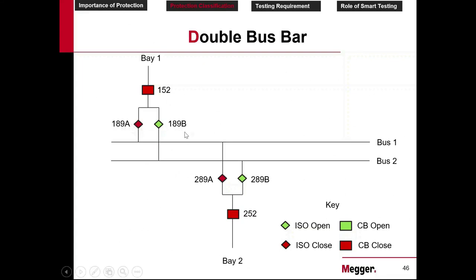A and B represent the isolators: A is the isolator connected to bus 1, B is the isolator connected to bus 2. So 189A means bay 1, the ANSI code of isolator, that is 89, and A represents the bus 1 connection. In this you can have 20, 30 or 40 bays. It will be the same thing repeated in that nomenclature. So let's follow the red line, how the current is feeding or transporting. It's like this. This is open, so it goes like this. Bus 1 is charged, it goes like this, and it goes like this. Same fault in bus 1 as we have seen in the earlier example.